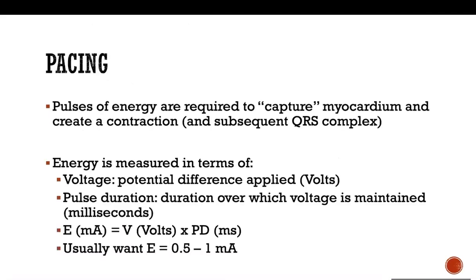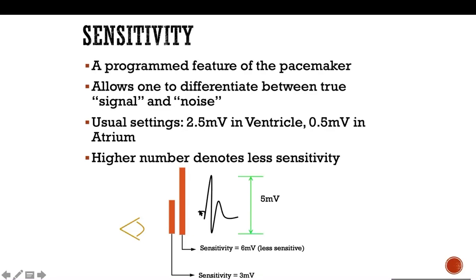So this is kind of an example. Let us say the device sees this QRS and measures the amplitude of it, and it says, okay, this is 5 millivolts. If we program the sensitivity at 6, the device is not going to see anything below 6. So it's less sensitive because it's going to miss a majority of the QRSs. If we program the device at a sensitivity of 3, that means it's going to see the majority of the QRSs since almost all of them are 5 or more. So this is how the device sees it. This is kind of an illustration, and the same thing happens with the atrium, but with different numbers.